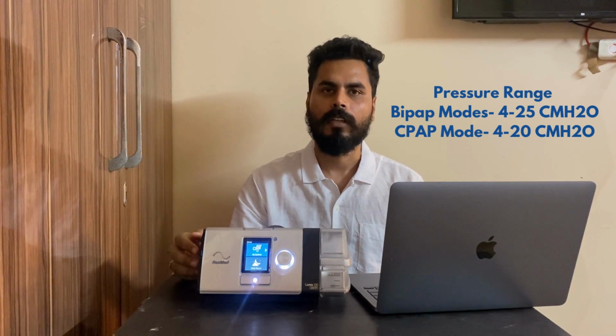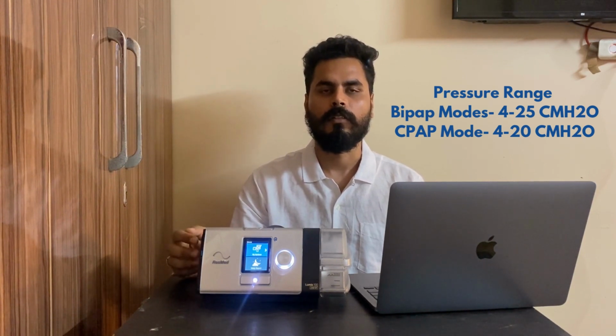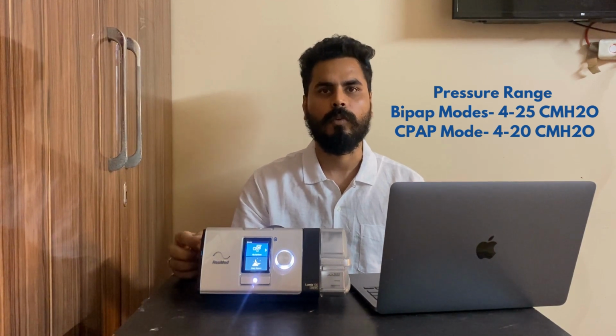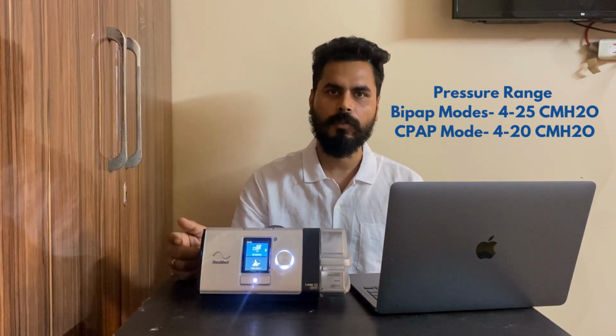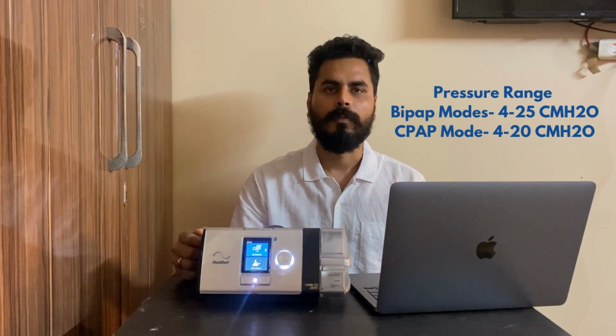If we talk about the features of this product, the pressure range and the modes, this machine essentially has 5 modes in it. One is CPAP, one is S, one is T, one is ST, and another is PAC mode. Pressure range on this machine, when you're using it on a Bipap mode, will be 4 to 25 centimeter of water. When you're using it on a CPAP mode, it will be 4 to 20 centimeter of water. Now this is a medical device, so what mode and pressure has to be given will be decided by your physician.